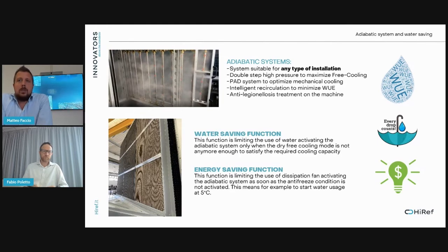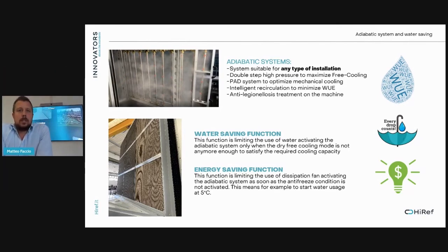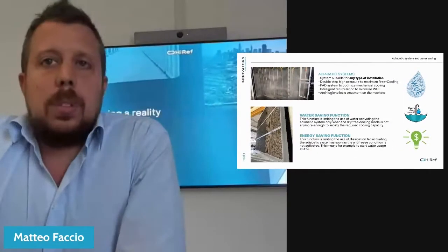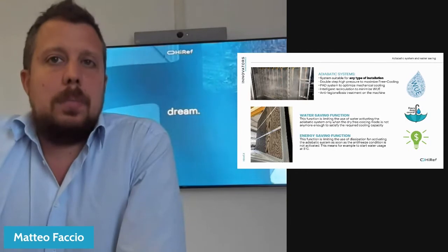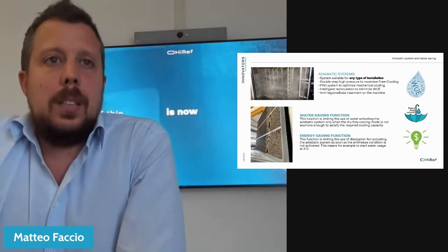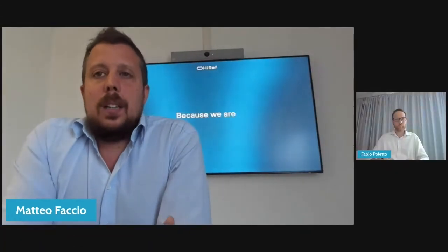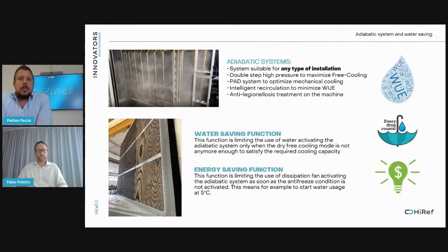So for that reason, we can activate two different functions. The water saving function, as the name says, limits the use of water up to the limit where the unit is no longer able to work without it. Or we can activate the energy saving function. In this case, for certain latitudes or regions where water is not a problem and is cheap, we can use water as much as possible in order to decrease the energy consumption. We need to keep in mind that, normally, apart from renewable sources, producing energy uses a lot of water, wasting water. So if we can save energy in the data center cooling, it means we can also save water in the electricity production.